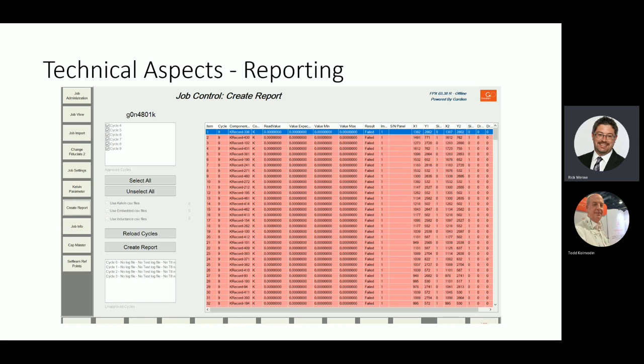So detailed. So every measurement we do for 4-wire Kelvin, you give the location, you give the label, you give the read value, the expected value, the minimum value, and the maximum value. And we put some more information in there, like the cycle information. Most likely at this level of test, you're going to put some serial number in there. So either the machine will scan the serial number, or the operators type in the serial number before the test, so it's all linked together.